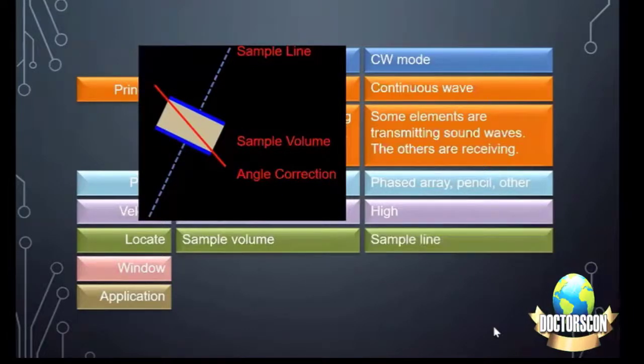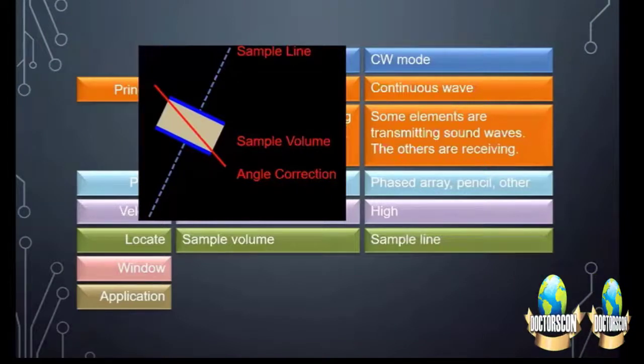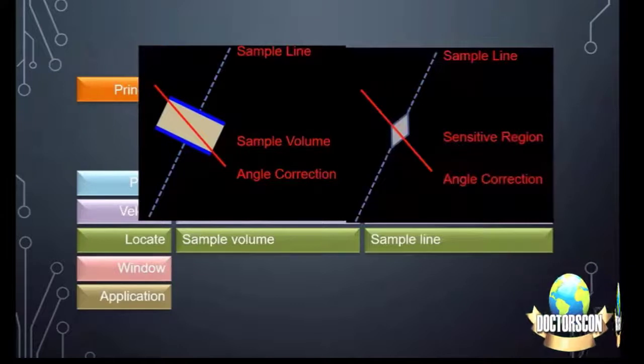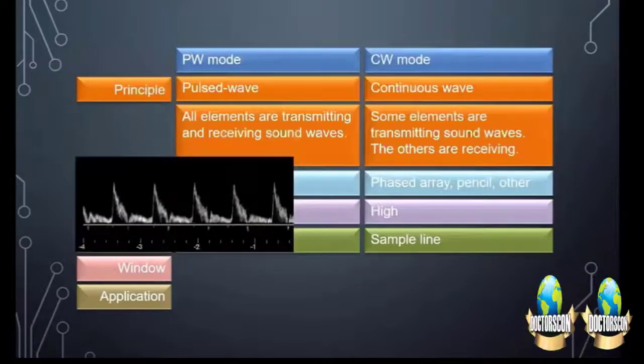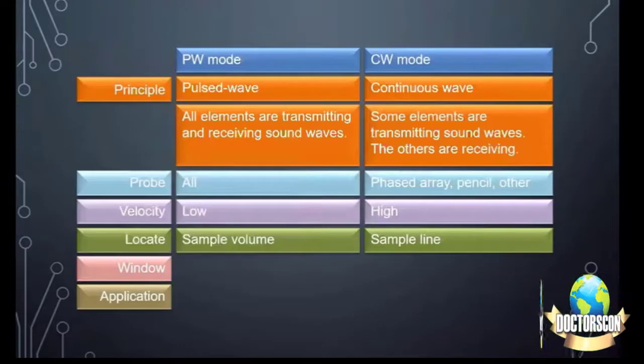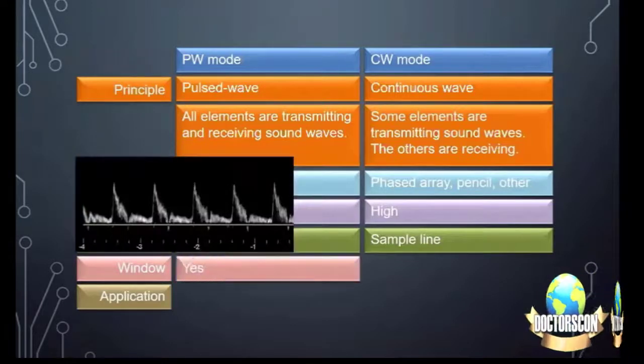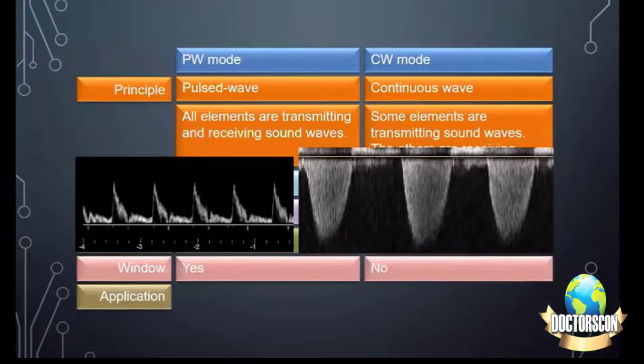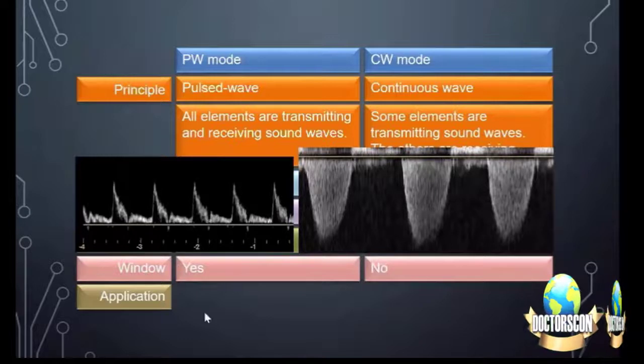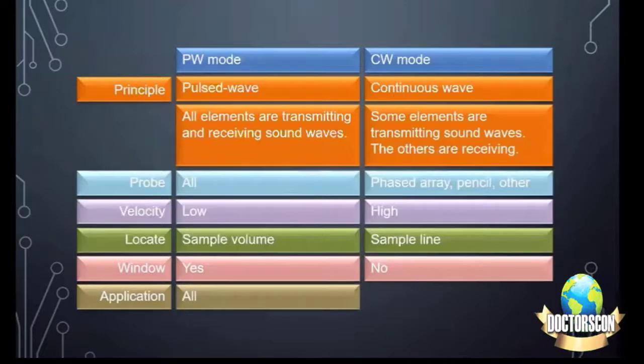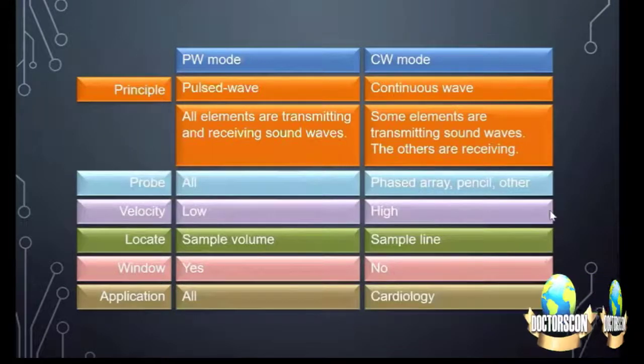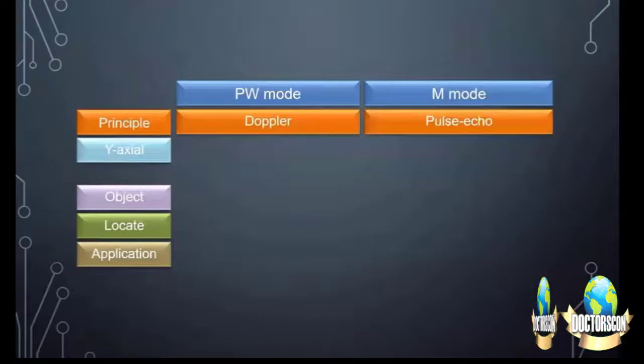We are taking the sample between the two blue lines. And for CW, just a sample line is required, not a sample volume. Then we locate the sample volume, then this is the spectrum, and this is how we get it on CW. In pulse wave we need a window. Here we don't need a window, it is just a line. Applications are everywhere, and CW is used for cardiology.